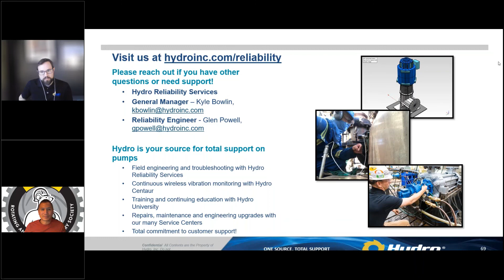So the best you can do is try to design it to avoid them, and at least understand what your natural frequencies are. Also at the design level, you want to have that prediction, because if you go out in the field and see a wildly different situation, that might be your first tip-off that something's not right with your installation. Maybe you've got massive pipe strain, a twist and force in the case, and as a result you're getting natural frequencies that shouldn't be there. So having that design-level reality check is always going to be important.